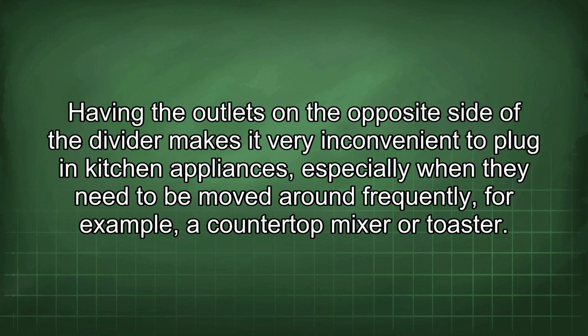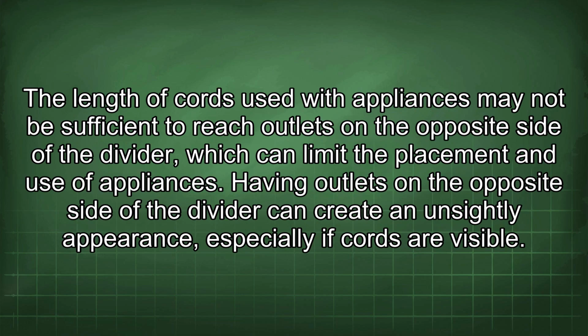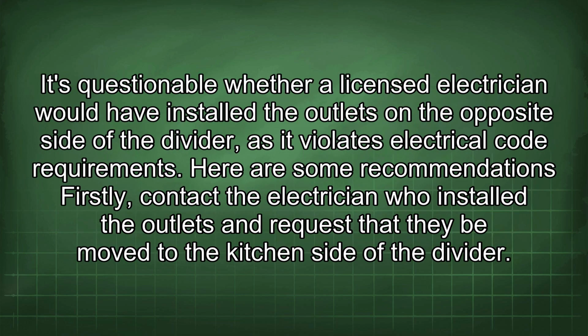Having the outlets on the opposite side of the divider makes it very inconvenient to plug in kitchen appliances, especially when they need to be moved around frequently, for example, a countertop mixer or toaster. The length of cords used with appliances may not be sufficient to reach outlets on the opposite side of the divider, which can limit the placement and use of appliances. Having outlets on the opposite side of the divider can create an unsightly appearance, especially if cords are visible. It's questionable whether a licensed electrician would have installed the outlets on the opposite side of the divider, as it violates electrical code requirements. Here are some recommendations.